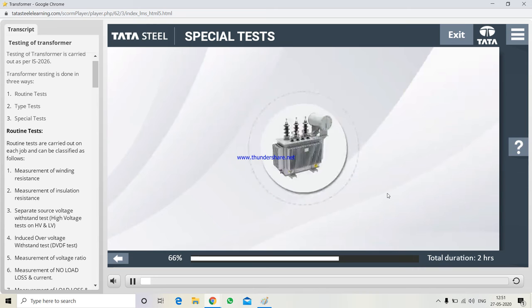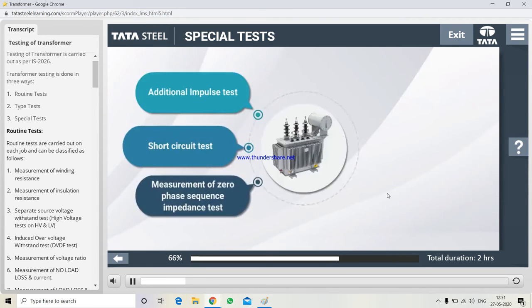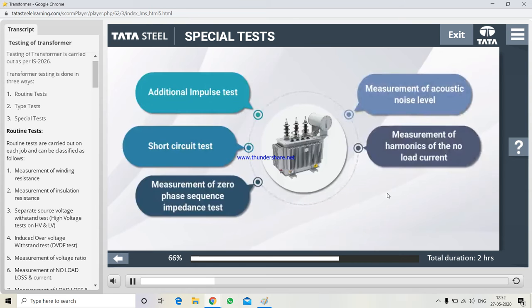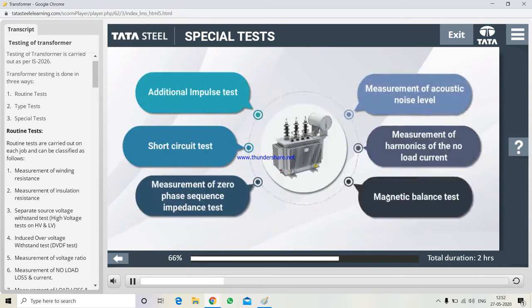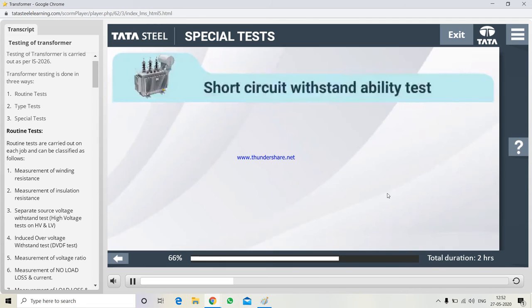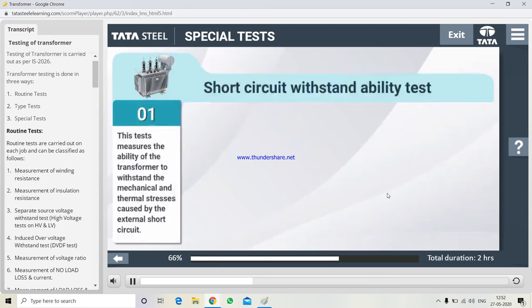Special tests can be categorized as follows: additional impulse test, short circuit test, measurement of zero phase sequence impedance test, measurement of acoustic noise level, measurement of harmonics of the no load current, magnetic balance test, short circuit withstand ability test. This test measures the ability of the transformer to withstand the mechanical and thermal stresses caused by the external short circuit.